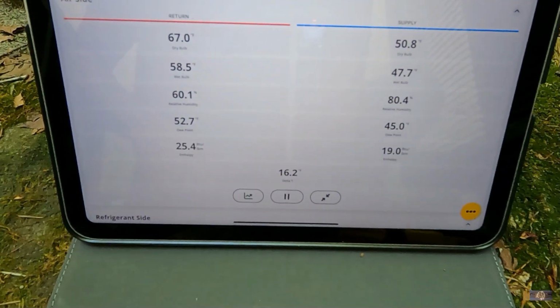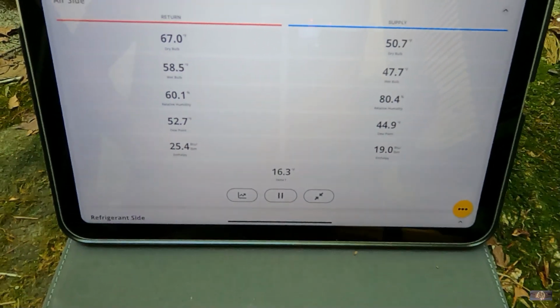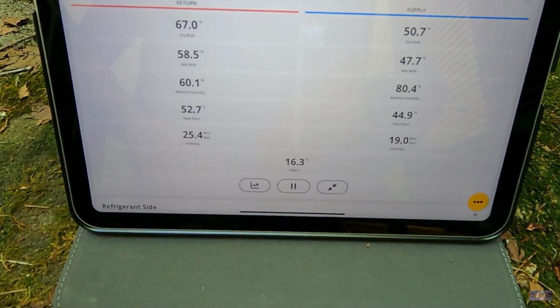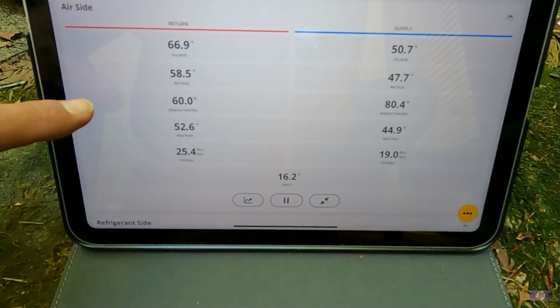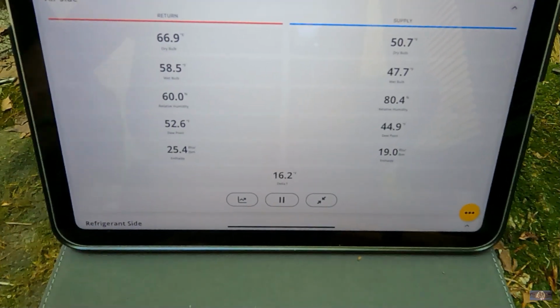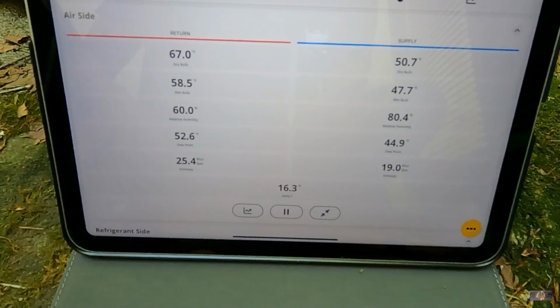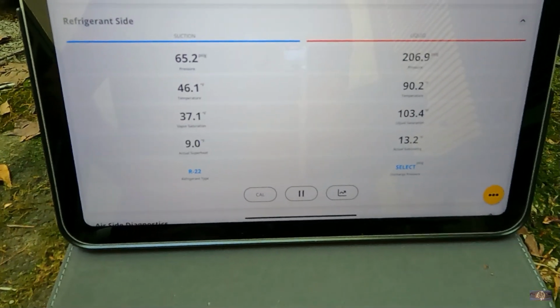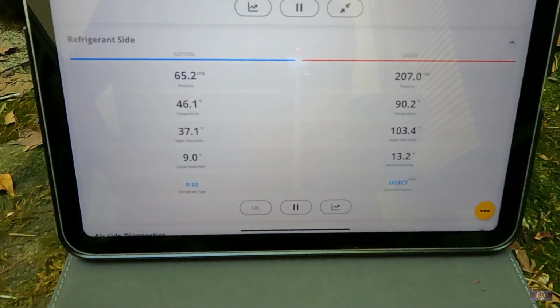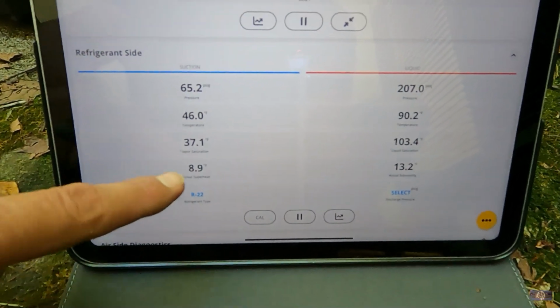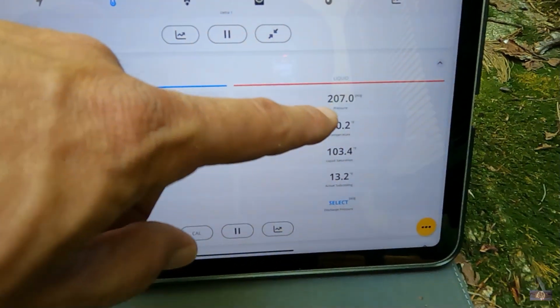Alright, so we're getting about a 16.2 degree split between return and supply, 16.3. Getting a little better. Been running a while now. It's probably about the best we're going to get.